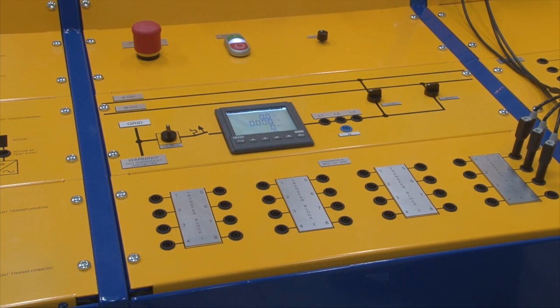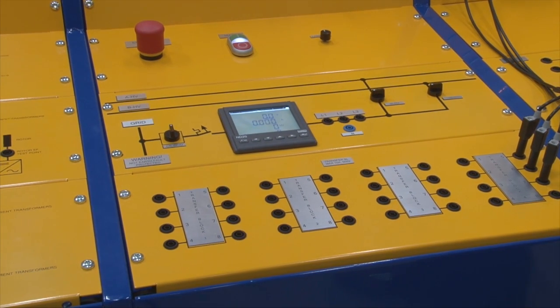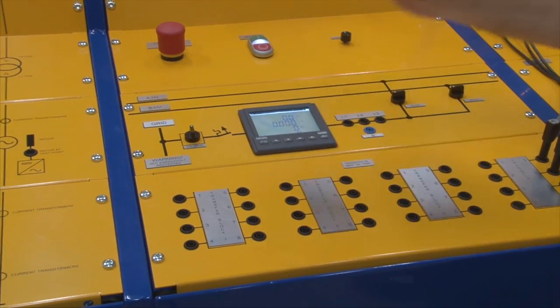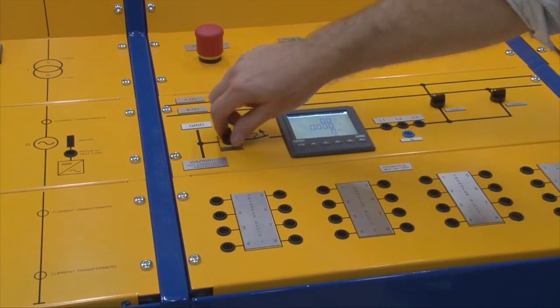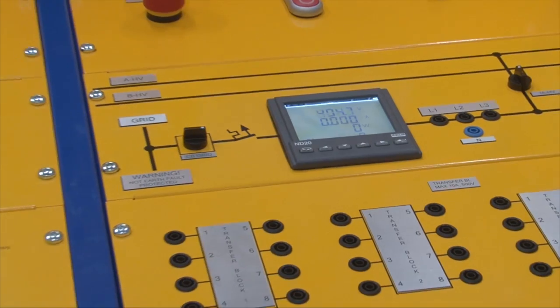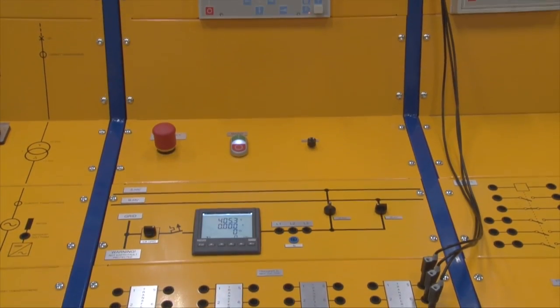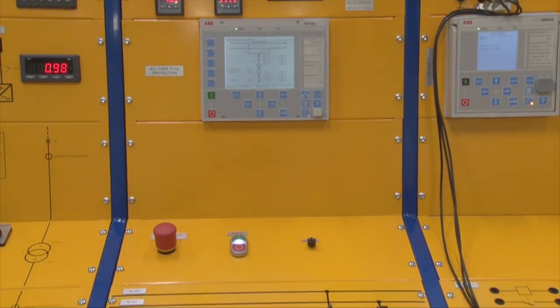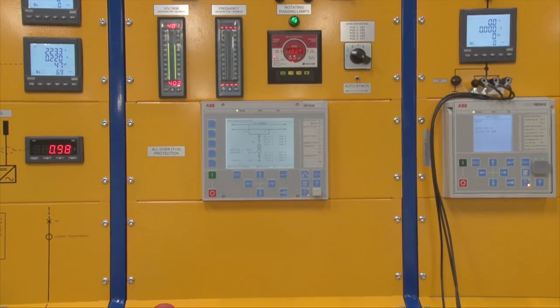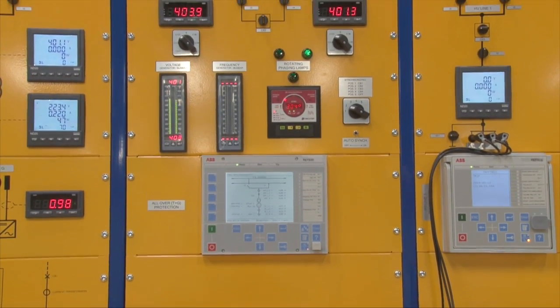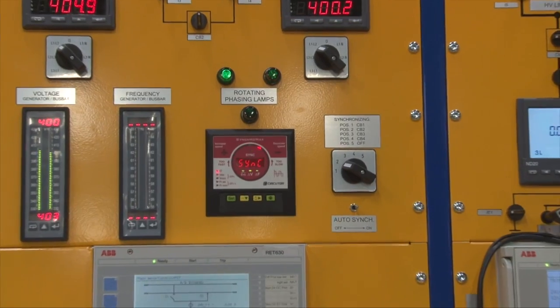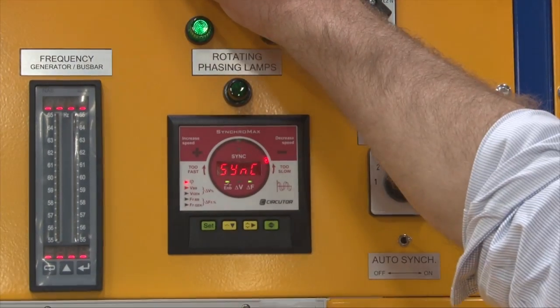Once a generator station is producing power, we may then want to connect it to an existing online network, or we may want to pair it with a second generator for increased capacity. The grid panel gives access to the external power network, and together with a comprehensive array of synchronization tools, critical parameters can be monitored and adjusted in order to synchronize between the grid and one or more generators.